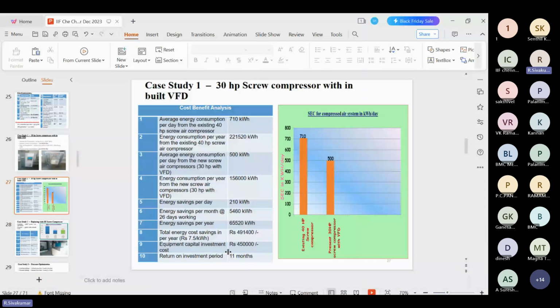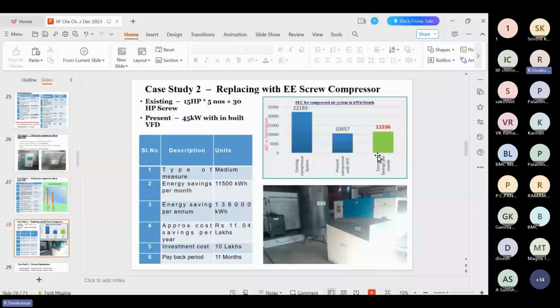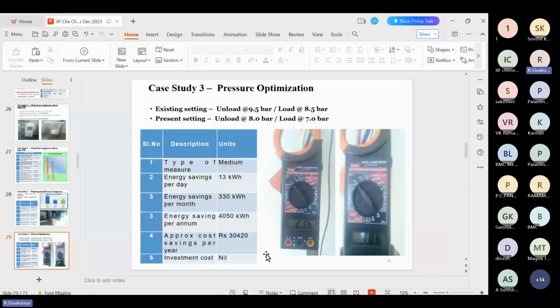Another example is replacing with a screw compressor. In the old system, they had five 15 HP reciprocating compressors and a 30 HP screw compressor. All were replaced with a 60 HP, 45 kilowatt compressor with inbuilt VFD. The energy saving per month is almost 11,536 units. In a year, 1,38,000 units were saved, and the approximate cost saving is nearly 11.04 lakhs, with an investment cost of 10 lakhs. The payback period is also 11 months. And pressure optimization needs no investment because it is one of the best operating practices.